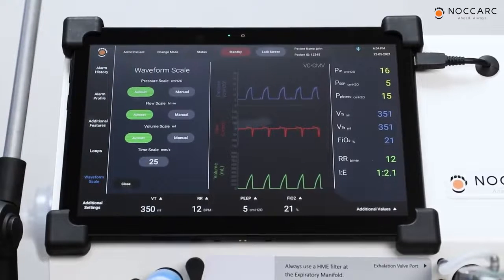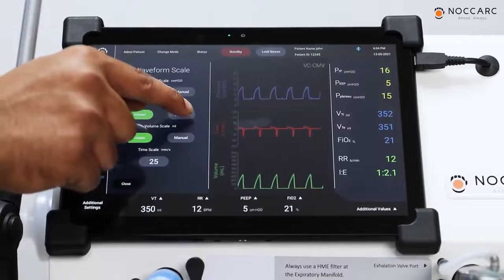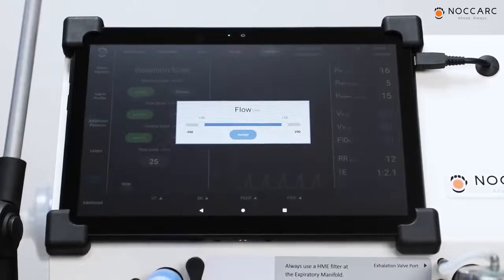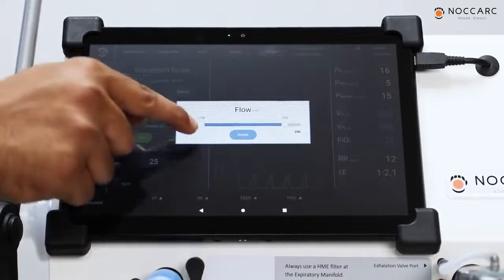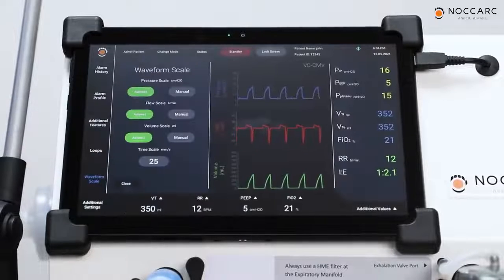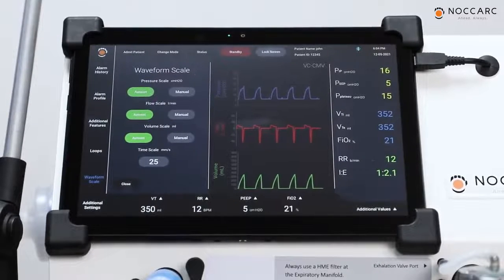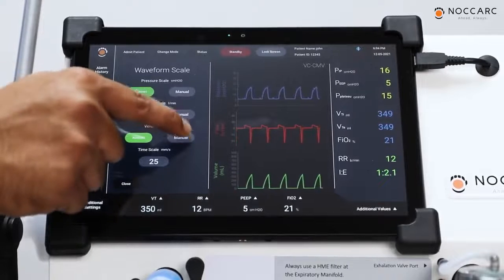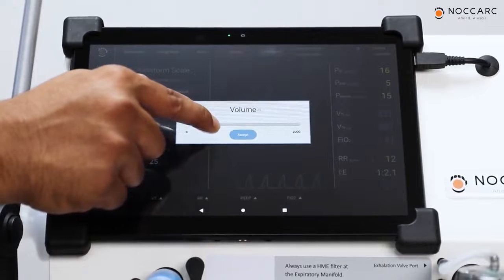Similarly, I want to change the flow scale. I will press on manual. For flow, the readings are provided from negative to positive. The reason behind it, during expiration, flow will go in the negative values. So I will change accordingly as per my requirement. I will accept it. Similarly, I will change the volume scale by pressing on this manual button. My targeted volume is 350, so I will keep it at 450. I will accept it.